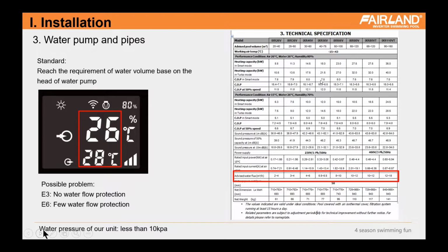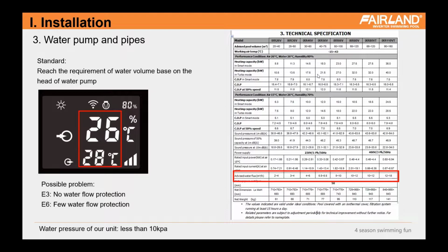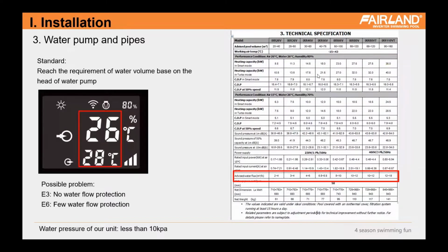And the last one is the water pressure. When you choose the water pump, the installer or the customer will consider the water pressure from the heat pump. And our heat pump has almost zero water pressure. It's less than 10 kPa, which means you can ignore this water pressure when choosing your water pump. So that's the installation part, normally including the installation space, the power and cable, and also the water pipe and water pump water system. Do you have any questions about this part, the installation?